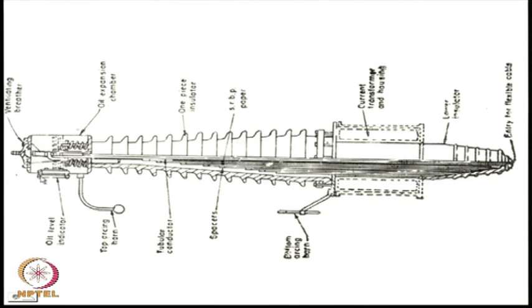This tank is normally oil filled. This provides a space for expansion of the oil, so that with variation of temperature, and this normally is insulated with SRBP paper. So, this is the construction of an oil filled bushing.